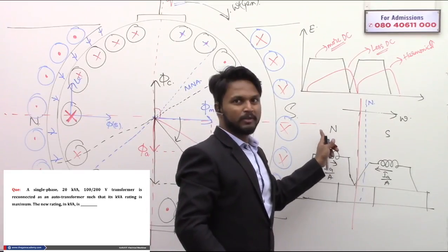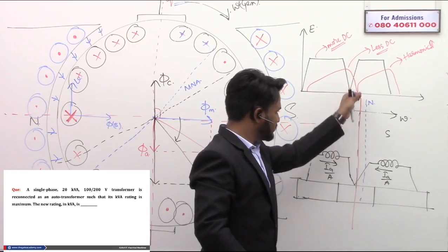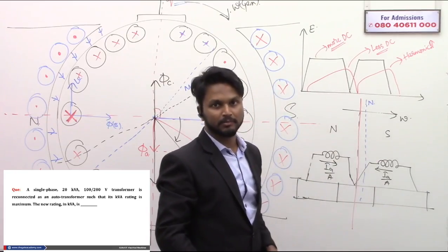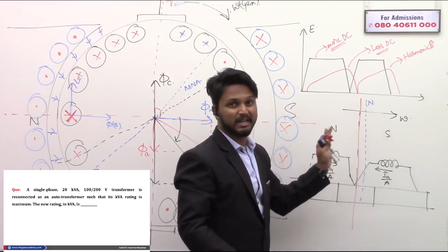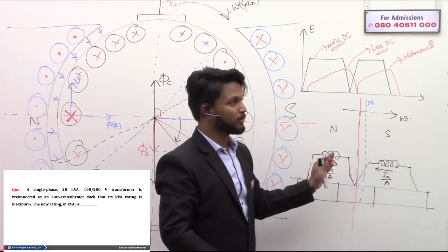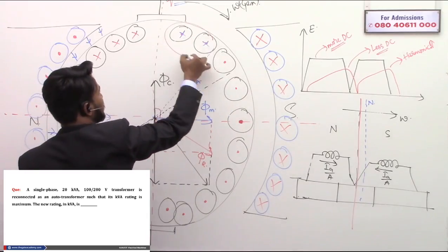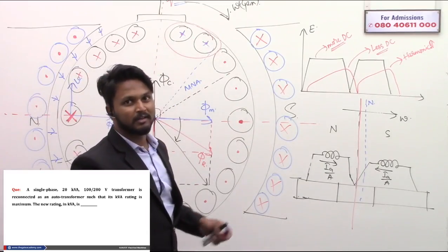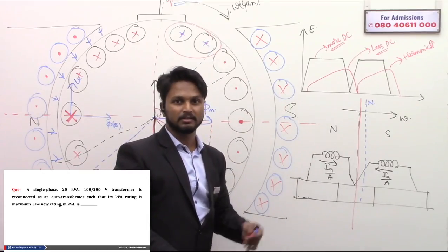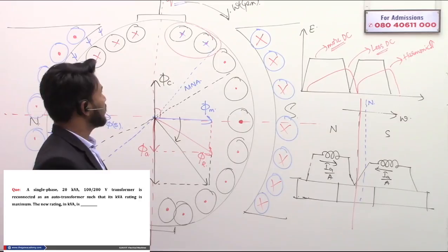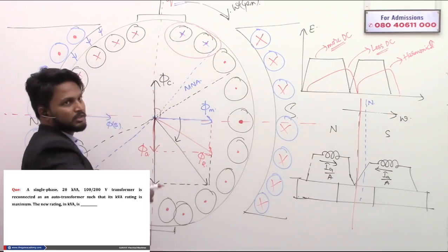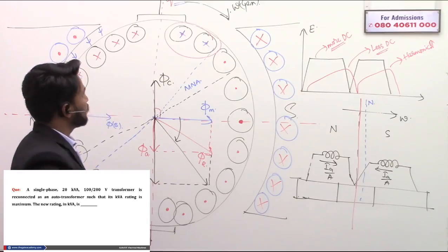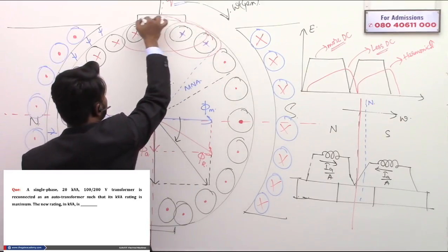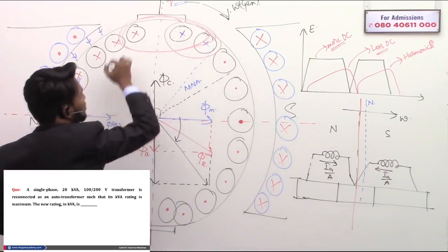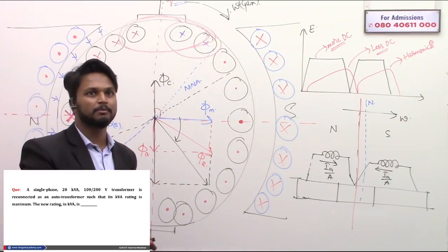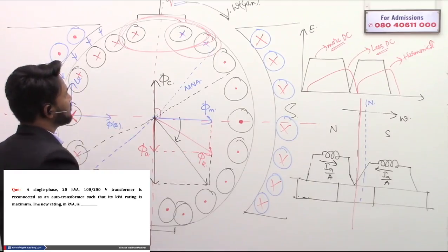So when it is moving from the north pole's influence to the south pole, there is a zero EMF point encountered here, but it doesn't become zero because the influence of the north pole has extended - the magnetic neutral axis has shifted. Some EMF is still inducing in them due to the north pole. So to place the brushes at the same position as the Q axis, we have to nullify the EMF under the conductors in this region.